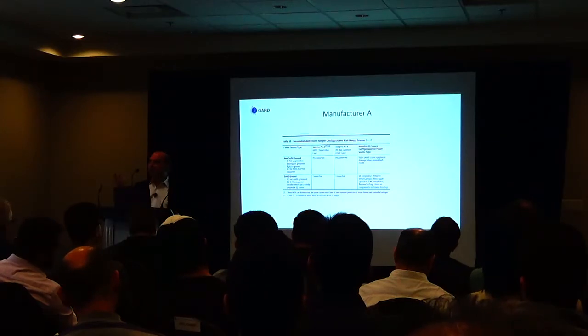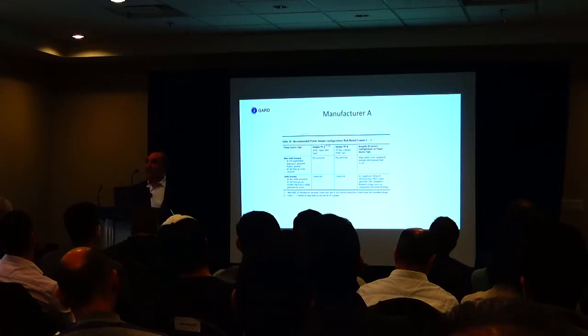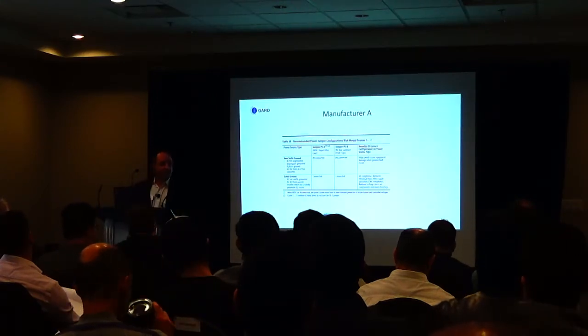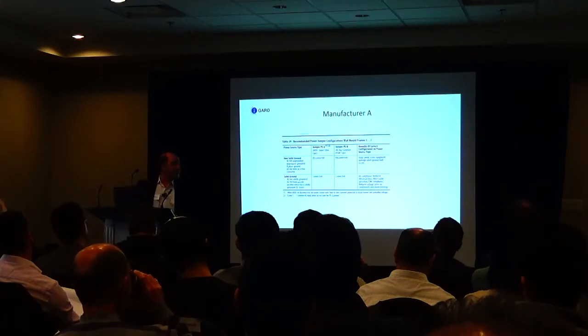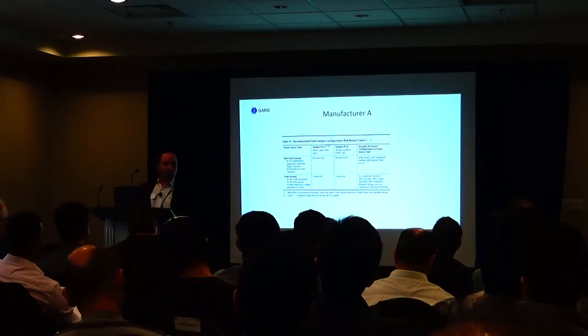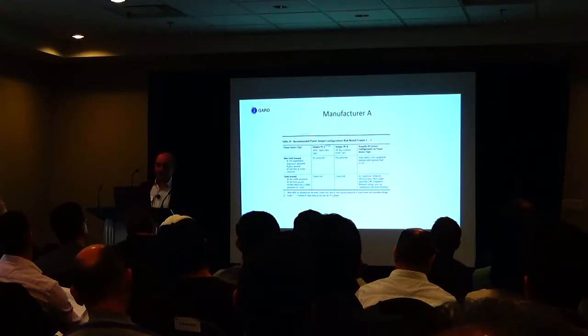what you're looking at here is you have to disconnect the MOVs, and we saw what happens with MOVs if you have elevated potentials on 2 phases. And unfortunately with the B-phase grounded system, you're going to have 2 elevated voltages on A and C. So you're going to have 600 volts on A, 600 volts on C, 0 volts on B, and your MOVs will do what they're designed to do. The equipment doesn't fail. All it means is the equipment is going to do what it's designed to do. The only thing that's failed is the person who installed it, because they didn't put the right jumpers in.